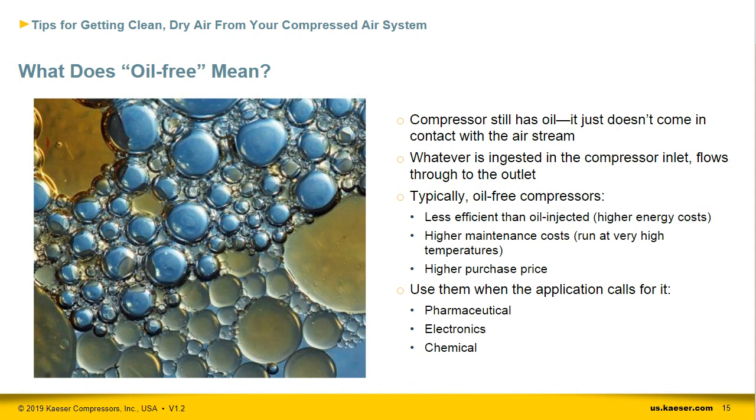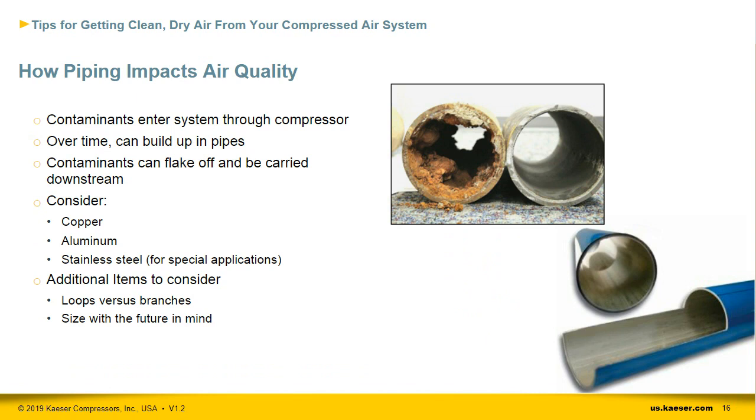A final point, and this is true for systems with oil-free or oil-injected compressors, don't forget about the piping. I've seen this on many occasions. Plants spend time and energy selecting, purchasing, and installing a bevy of compressed air treatment, only to have the clean, dry air pass into old, dirty pipes as well as tanks. Some piping materials are a source of contamination that can flake off and migrate to the production equipment.